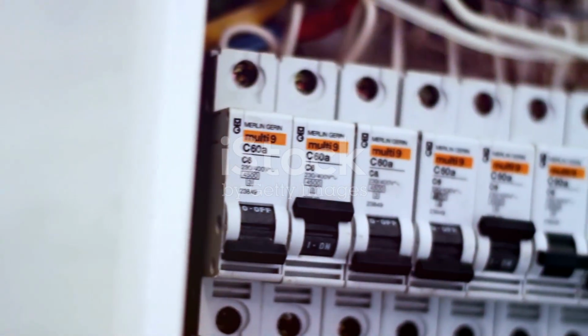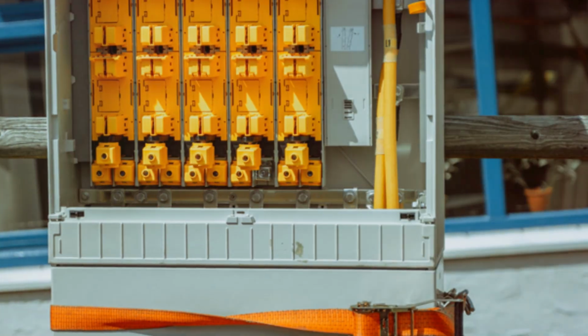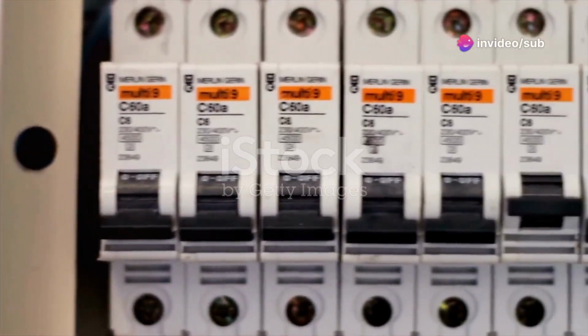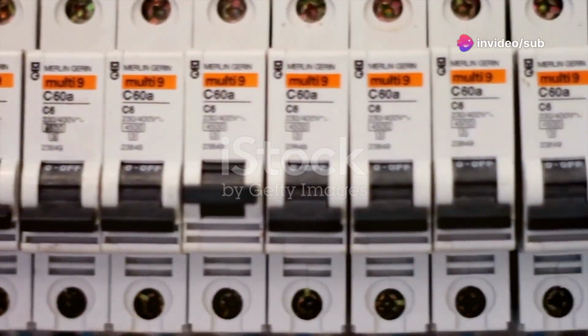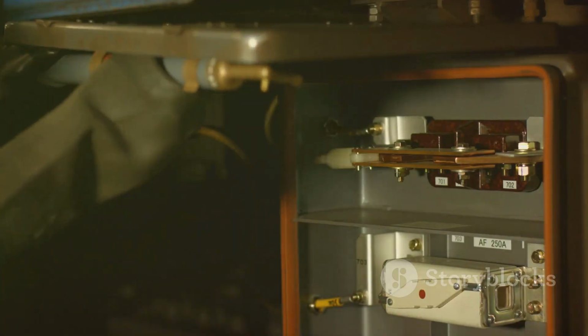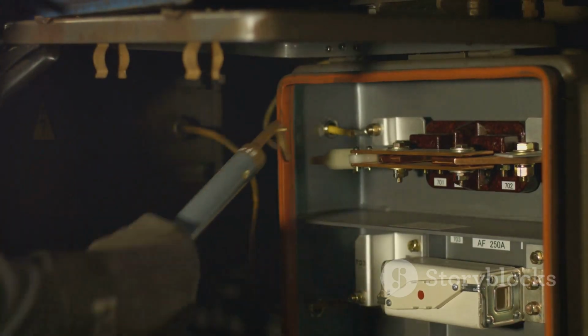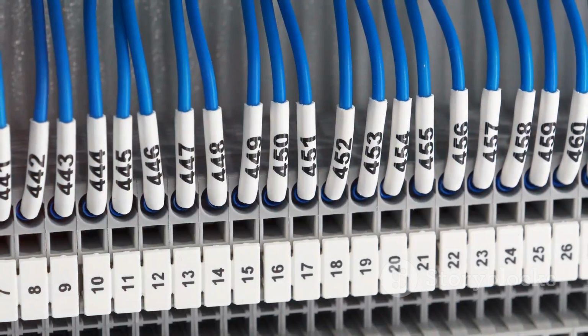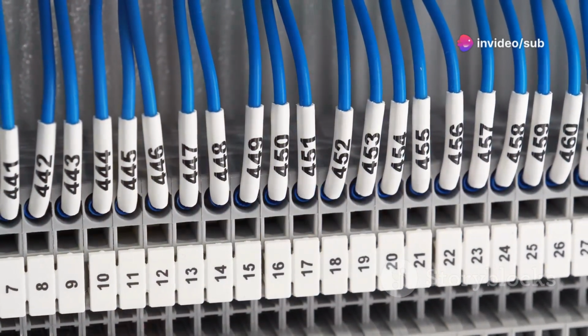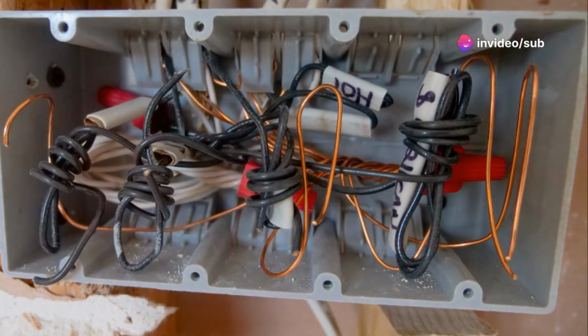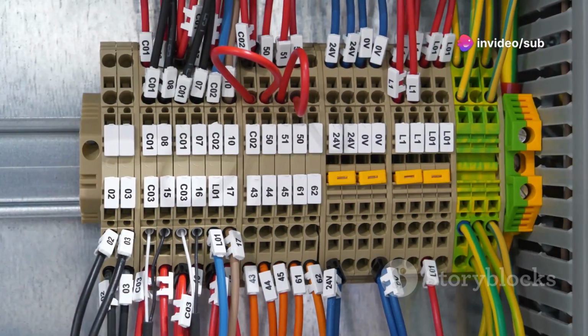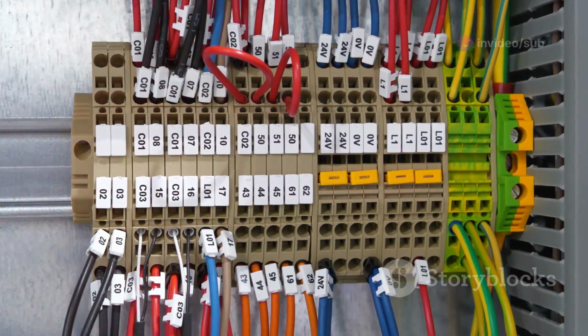Breakers with more than one terminal are designed for good reasons. Let's look at 3 of the most important ones: load distribution, wiring flexibility, and bus bar integration. First up, load distribution. Sometimes a single breaker needs to feed more than one circuit. Multiple terminals allow you to connect two separate wires, each carrying power to a different branch. This helps spread out the load and keeps your wiring neat.